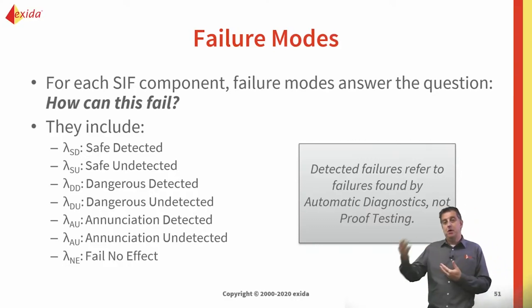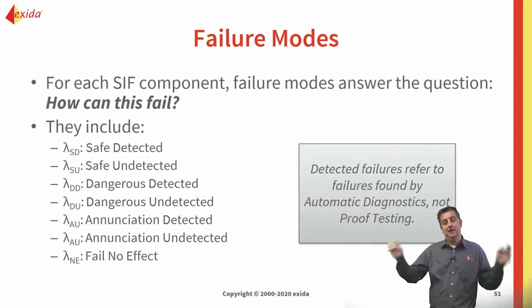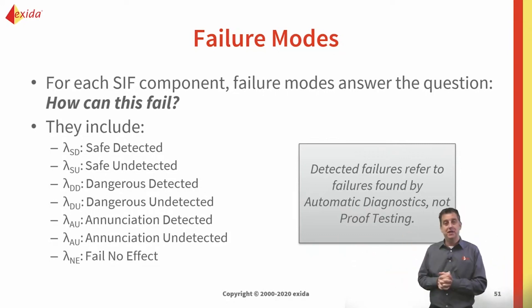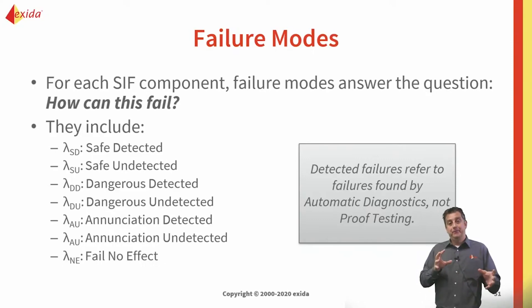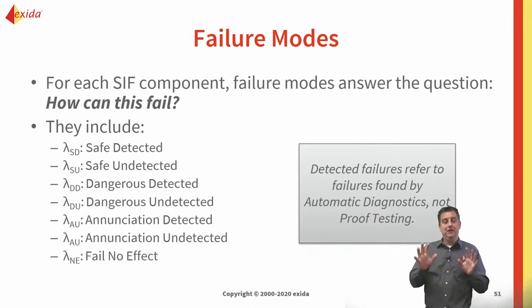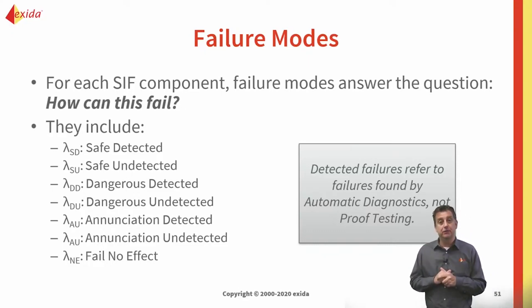For dangerous failures, splitting them into detected and undetected is essential because a dangerous failure won't be noticed during normal operation. You could have a valve out there that is stuck open, unable to go to the safe state, and you simply don't know it because it hasn't been tested or there's been no demand requiring that valve to move. By adding diagnostics to that valve, you may be able to detect some of those failures and convert dangerous undetected failures into dangerous detected failures.